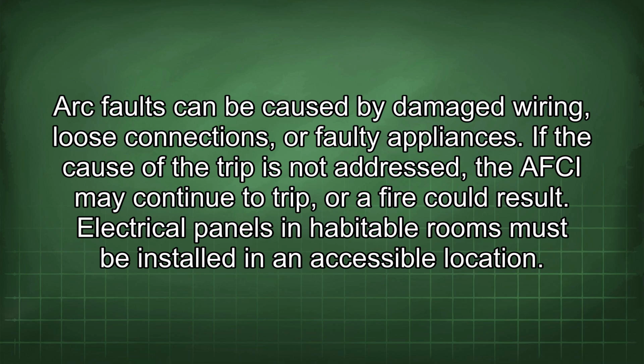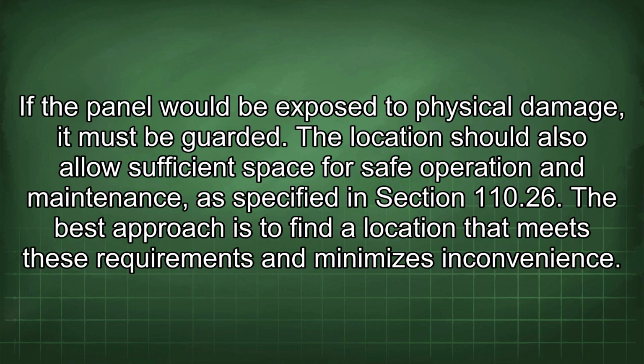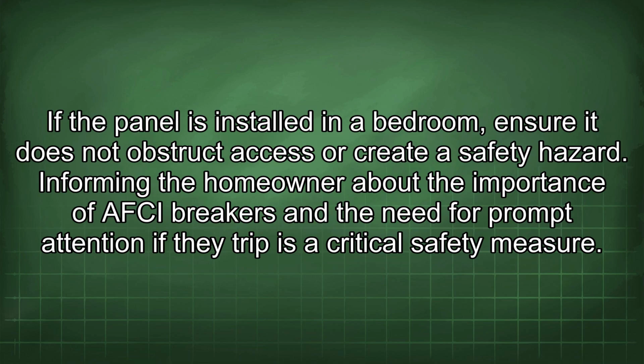Electrical panels in habitable rooms must be installed in an accessible location. If the panel would be exposed to physical damage, it must be guarded. The location should also allow sufficient space for safe operation and maintenance, as specified in Section 110.26. The best approach is to find a location that meets these requirements and minimizes inconvenience. If the panel is installed in a bedroom, ensure it does not obstruct access or create a safety hazard.